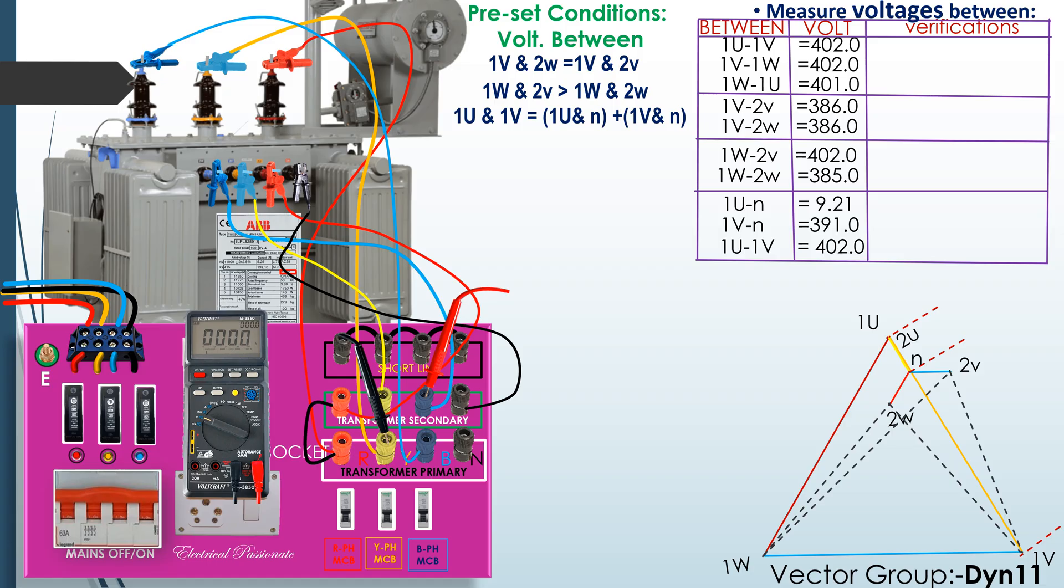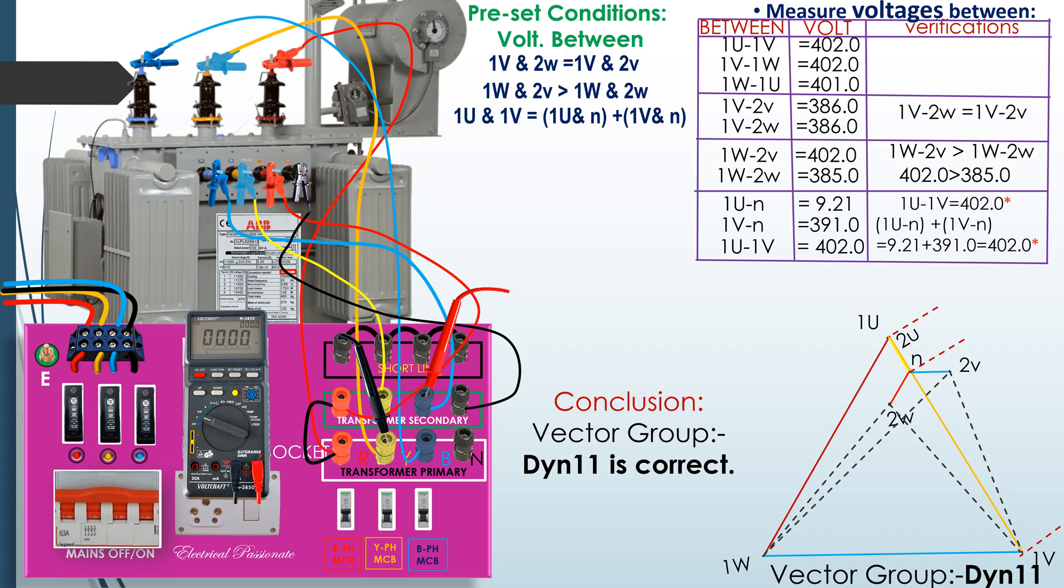Verify the obtained voltages with the preset conditions. The conditions are satisfied, so the vector group DYN11 is correct.